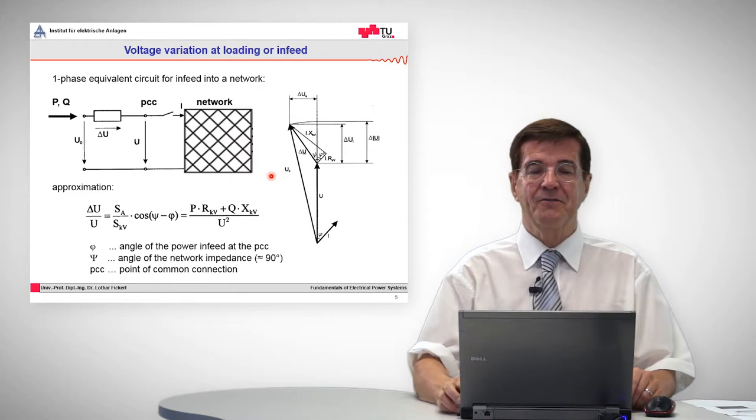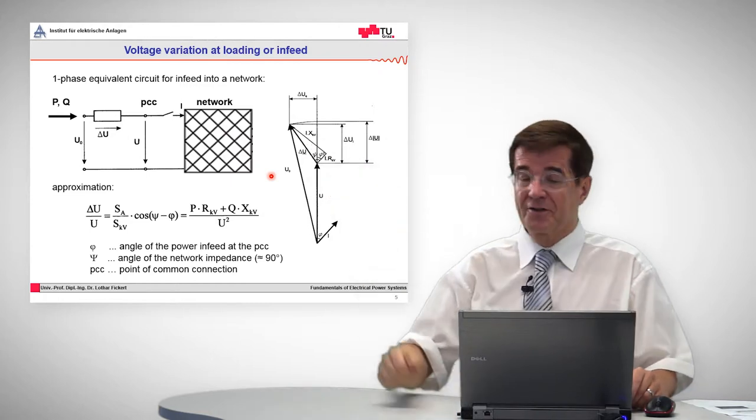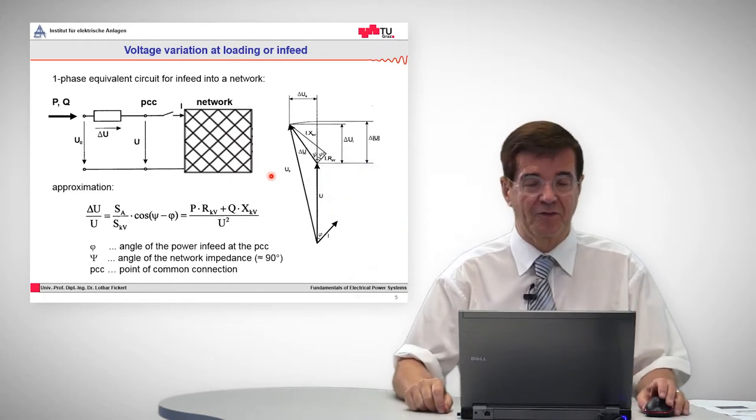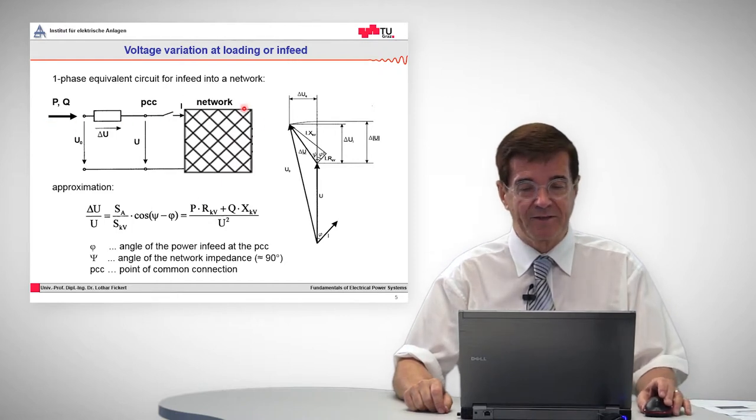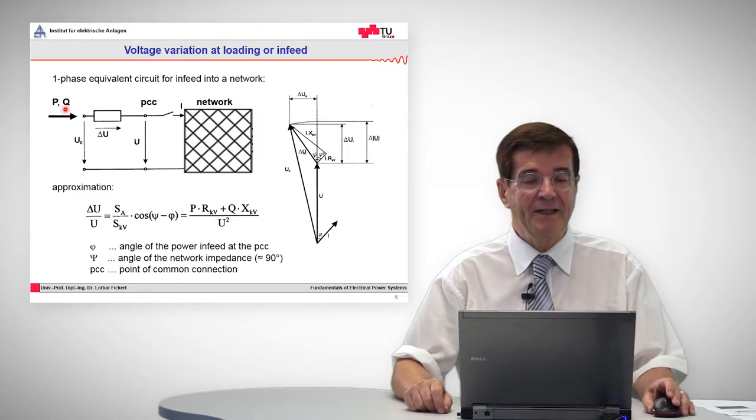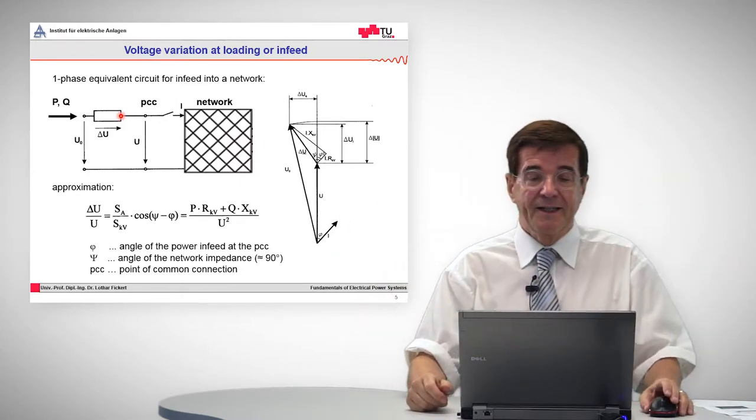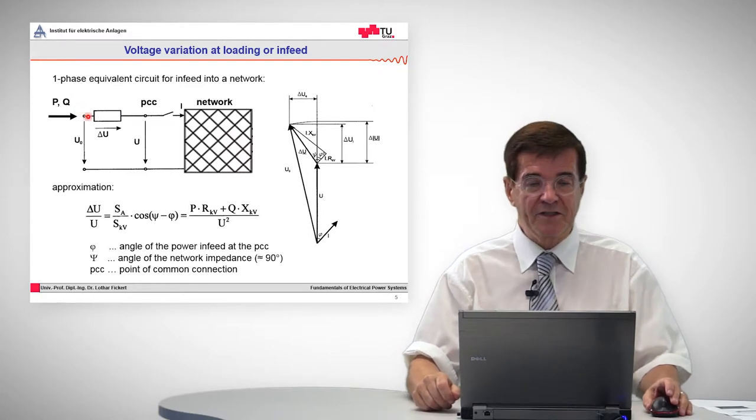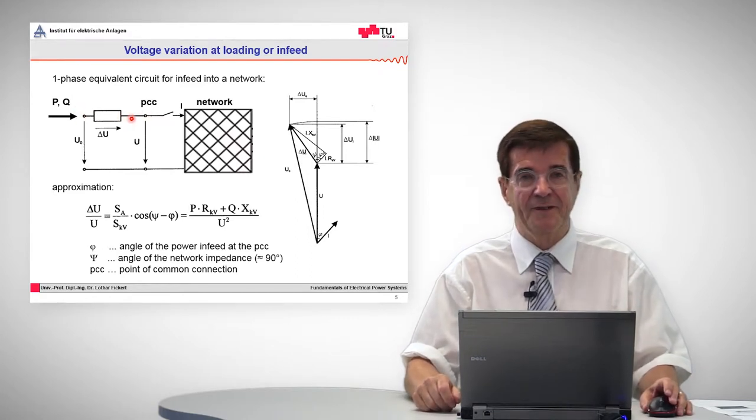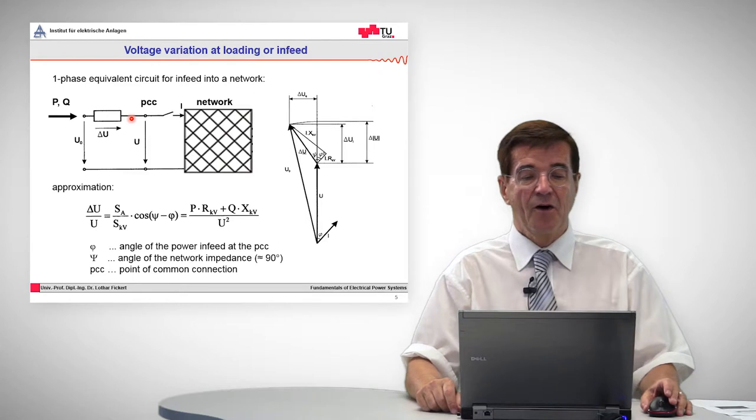Let's start with voltage variations due to infeed of load. Once into a grid, which is represented by this mesh network, power and reactive power are imported through an impedance, the connecting impedance between the generator and the net. Then there is a voltage drop across this line, we call it delta u.